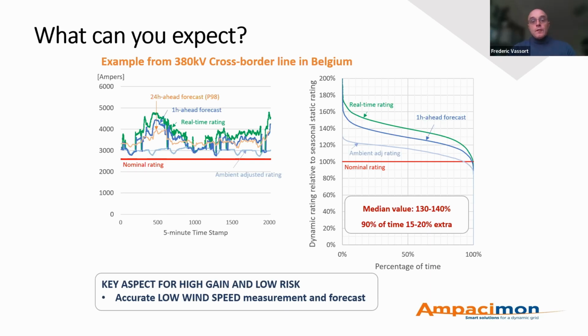Now, the real value of dynamic line rating is to be able to forecast it so that free capacity can be made available to the day-ahead market and can really be used in particular for interconnectors. And that's the orange curve on this same graph, where you see that, of course, the forecast is lower than real time by design, and that's what we strive to do in our algorithm, is never to allow the grid to be put at risk, and therefore the real time should always be higher than the announced forecast. But still, the forecast mode delivers, in this example, more than 1,000 amps extra capacity most of the time.